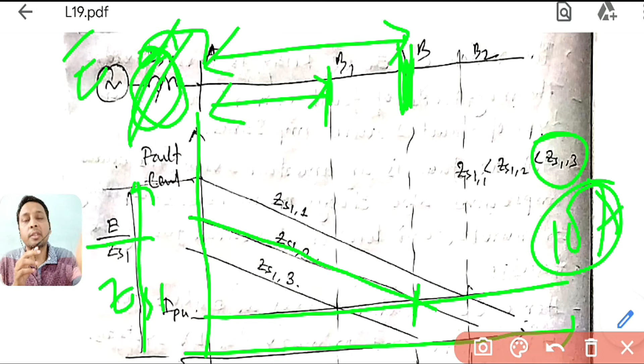Now suppose due to a change in the number of generators, your source impedance increases, ZS3 increases. As it increased, you will get this 10 ampere current here only, because the fault current will get reduced. So if you take less length, your ZL will also get reduced. This ZS plus ZL will remain the same, because this is increased, so you want to reduce this. So you will find the fault current of 10 ampere here only. So you can see your reach is now AB1.